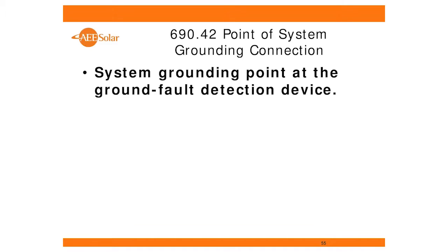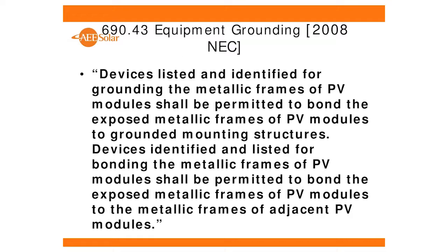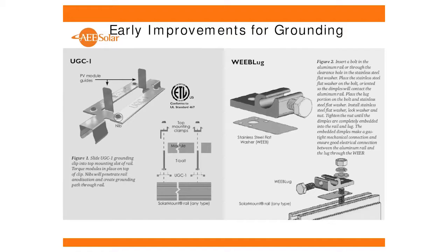So the system grounding point is at the ground fault protection device. I think we talked about that. And then there's talk about equipment grounding. This is where we get into all the arguments, the big issues on the table with AHJs, which are generally around how do we do proper bonding and grounding of PV modules, arrays, array structures, you name it. These are all valid and important questions.